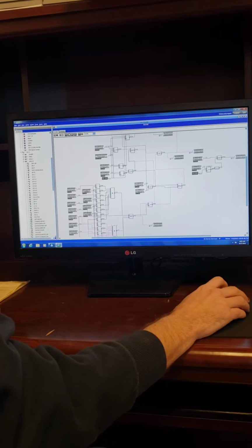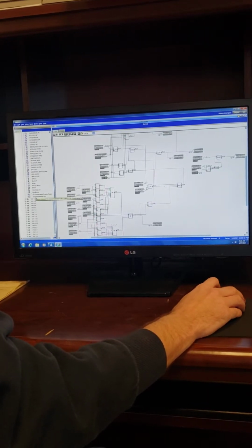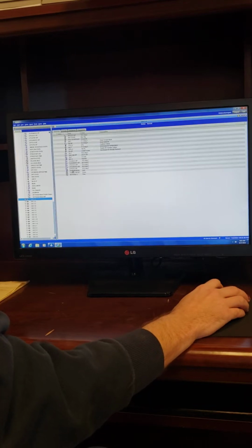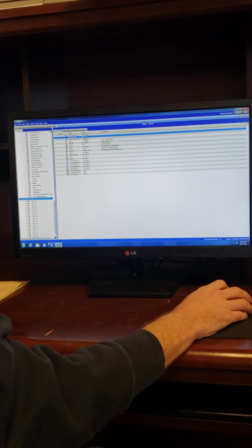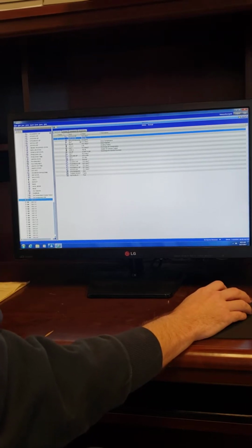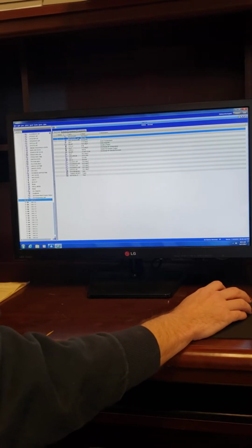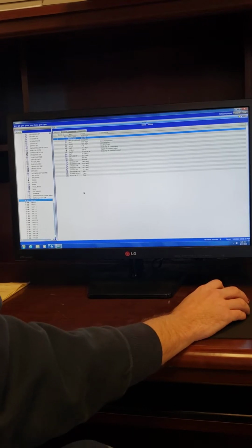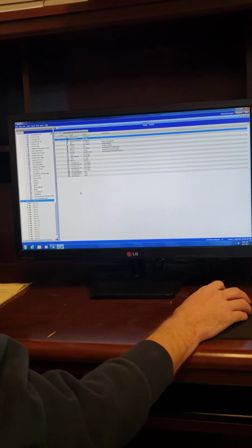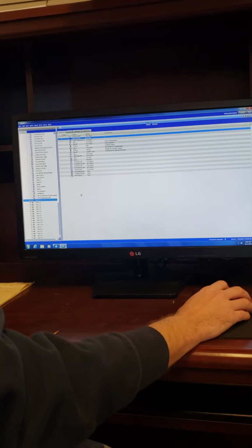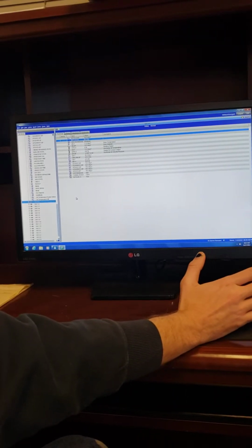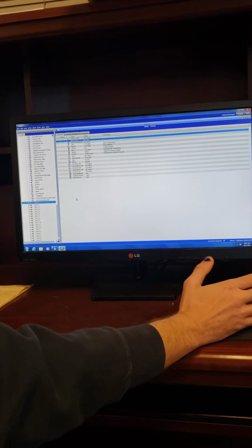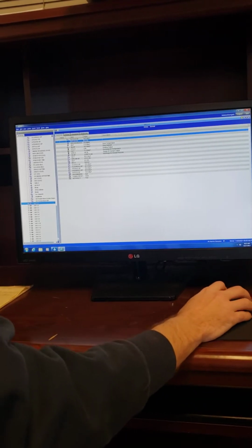So this is the zone state of VAV 1-1. We go over here. The zone state of VAV 1-1 says box heating. Essentially it's saying this one's calling for heat, and then it tallies up how many are calling for heat, and then it'll turn on your boiler. Because if you only had one room that was slightly cold, turning on your boiler to heat up one room is kind of wasteful on energy. That's why they have that for energy savings.